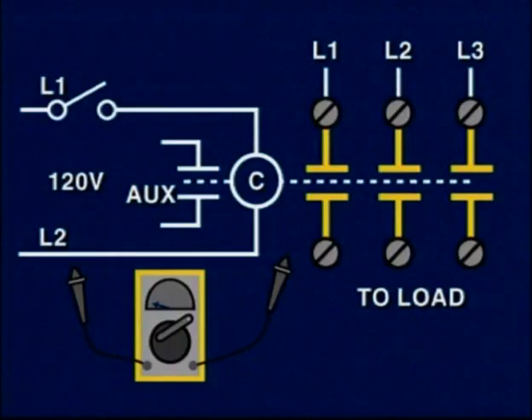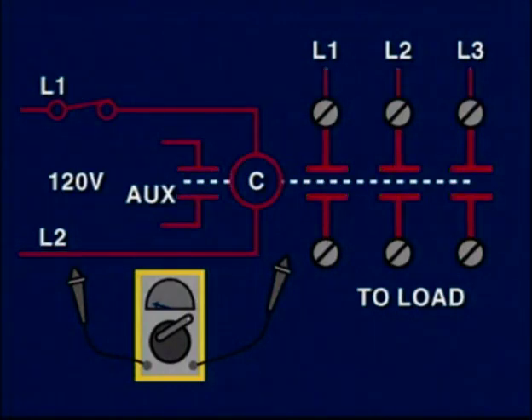During preventative maintenance, make sure that the arc suppression features of the contactor are present and working properly without any damage. Troubleshooting contactors is done similarly to relays. You need to make sure that the coil is being energized and that the auxiliary contacts, as well as the power contacts, are responding to the coil's energization.